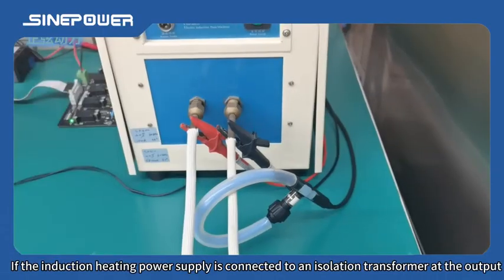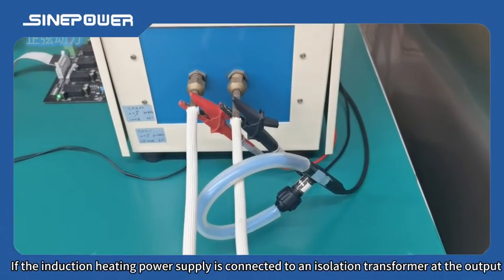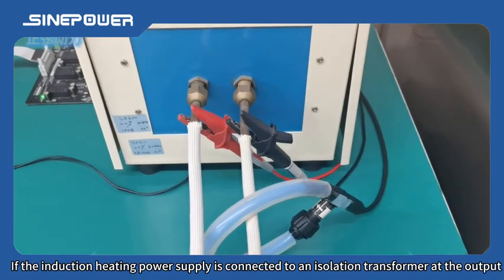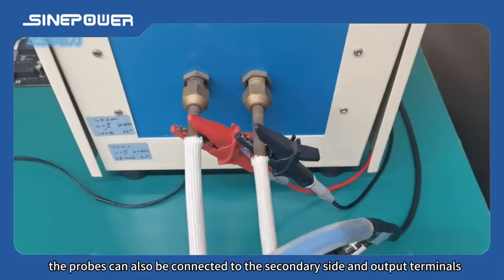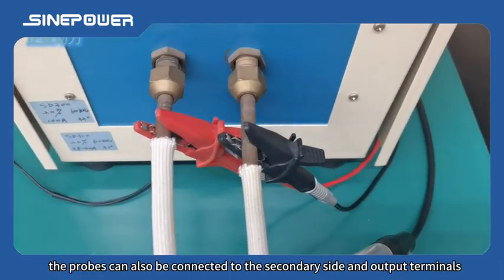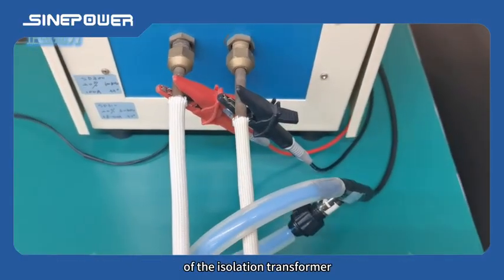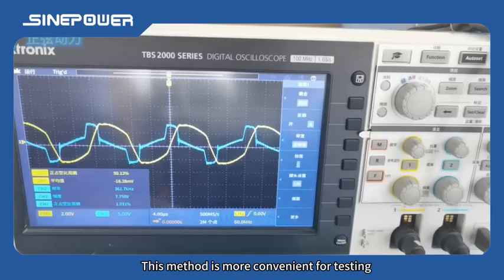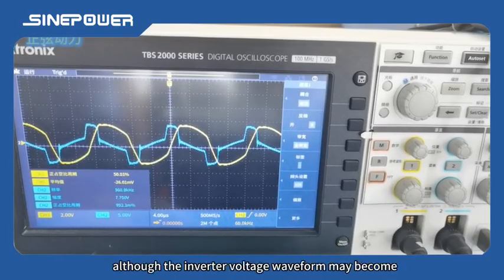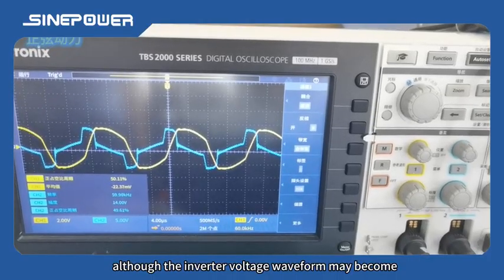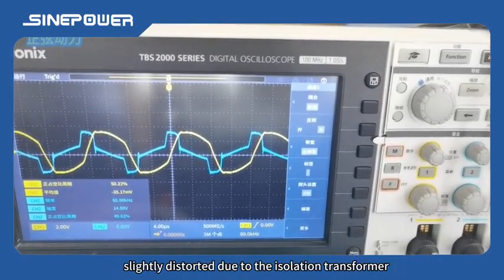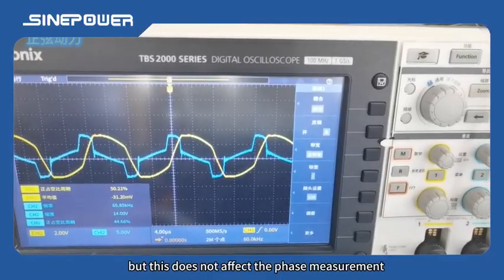If the induction heating power supply is connected to an isolation transformer at the output, during actual measurements, the probes can also be connected to the secondary side and output terminals of the isolation transformer. This method is more convenient for testing, although the inverter voltage waveform may become slightly distorted due to the isolation transformer, but this does not affect the phase measurement.